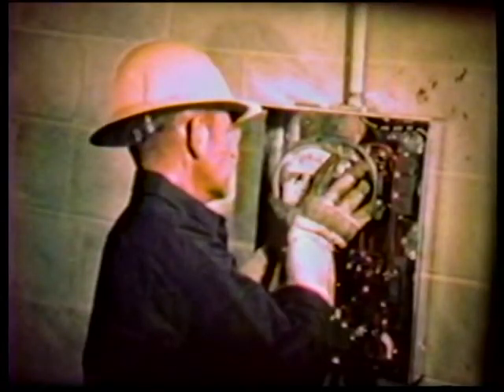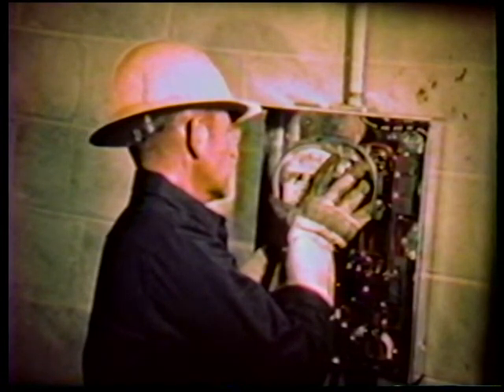The lower jaws are unenergized, so there is less chance for an accident. Then push the meter in. Do not pound. Also, notice the use of leather or cut-resistant gloves as a protection in case the glass should break. In the more complex meter installation using current transformer CTs, additional hazards exist.